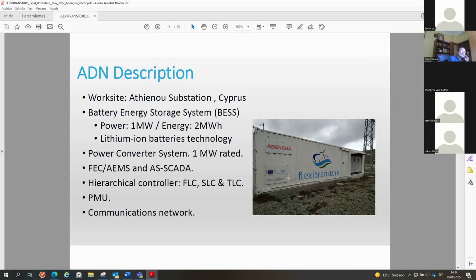Outside the converter, we only have one step-up transformer to connect the system to the external grid, and the SCADA, which is in a nearby building in the substation. Apart from the main components, the control system includes the front end controller and the energy management system, housed in the battery container. These are intended to manage the operation of the batteries and also control the generation, injection, or absorption of active and reactive power to the grid.